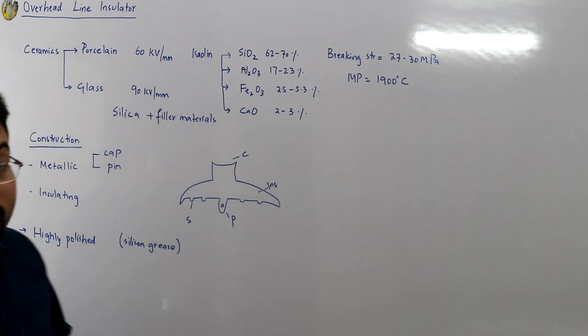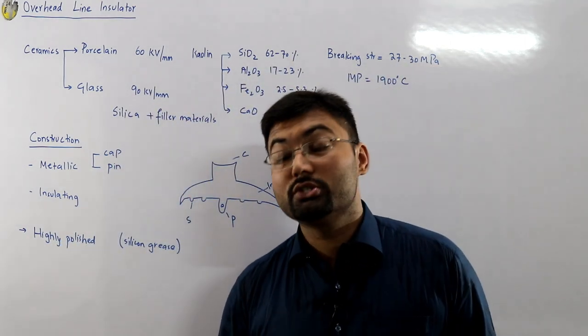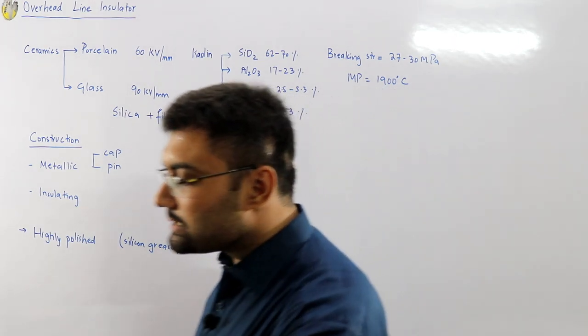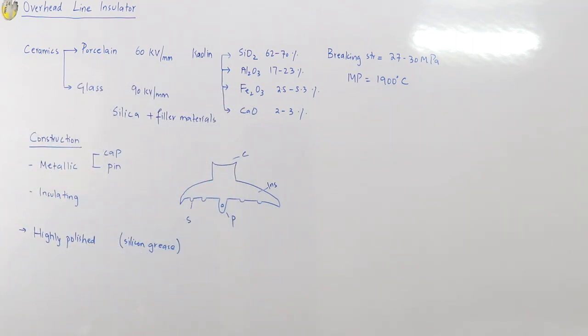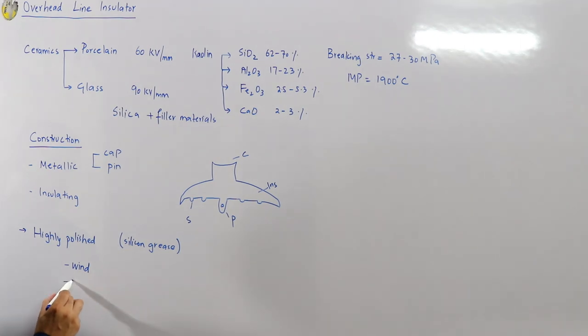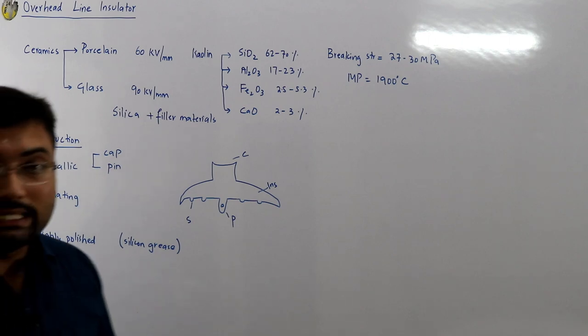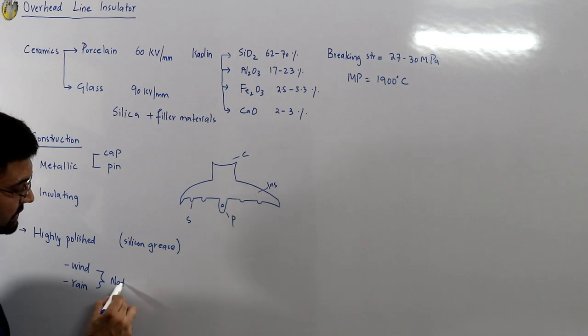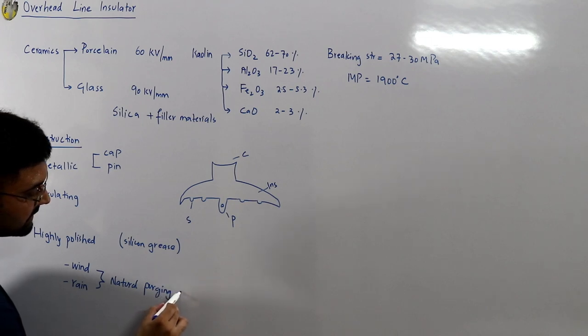Silicon grease is applied so that dust does not deposit on the surface. On a highly polished surface, dust either gets blown away by wind or washed away by rain. These two events — wind and rain cleaning — are called natural purging events.